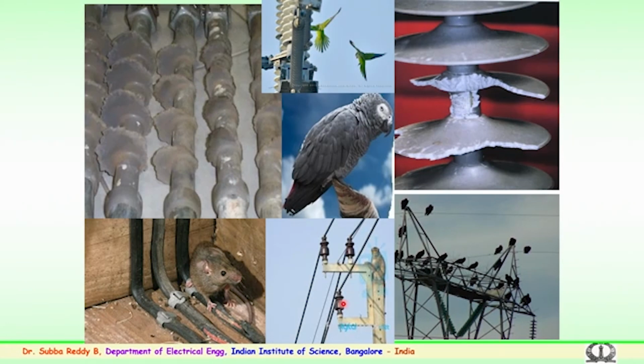But when you look at this slide, it may look strange why this slide has been put. This silicone rubber, polymer or porcelain type of insulator, as I was mentioning, is an organic material, so it is very important to take care. Sometimes the storing of the material is very important. If you do not store it in a proper way, small animals could damage the insulation, and also parrots and huge birds which normally reside on the tower of the transmission lines would like to peck the surface of the silicone rubber so that they could damage the sheds. This is again a small issue pertaining to birds and small animals. So, every care has to be taken as compared to a ceramic or glass insulator. These are to be much more attended to in the transmission systems.